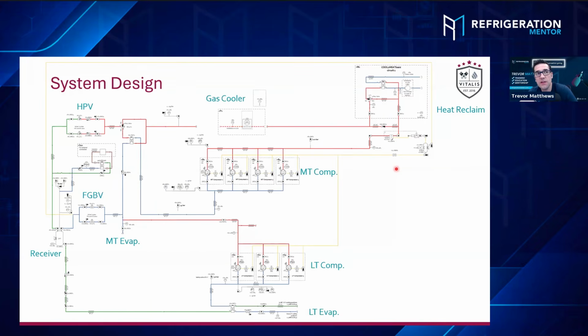I love what you just said there, though. This is something that's not lost yet, but it's the difference between an experienced technician and someone that is less experienced. Because I know friends that can walk into a rack room and they listen and they're like, I know that compressor right there, probably number 3, is the one that's running into it. There's something going on. It's not right. Or they listen to a valve and the way the valve is moving or opening and closing, they're like, there's something wrong in there, like there's a skip in the gear. And this comes with experience. I love that. It's touching, it's looking, it's seeing, it's smelling. Yeah, even smelling sometimes. And like listening, you can clearly hear if the system shuts down, but you still hear a little blowing noise coming out of a high pressure valve, flash gas valve, or injection valve.